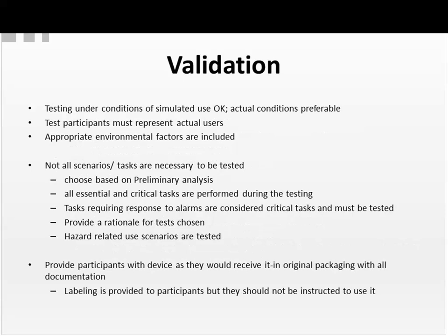Now, the test participants must represent actual users, and you must consider the environmental factors. Now, we've identified lots of use scenarios and tasks. Not all of these are necessary to be tested. All essential, all critical tasks must be tested.